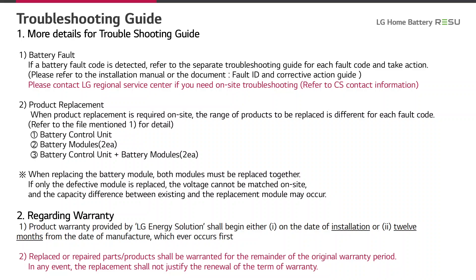When product replacement is required on-site, the range of products to be replaced is different for each fault code. It can be the battery control unit, the battery modules, or both the battery control unit and the battery modules. When replacing the battery modules, both modules have to be replaced together. If only the defective module is replaced, the voltage cannot be matched on-site and a capacity difference between the existing and the replacement module may occur.